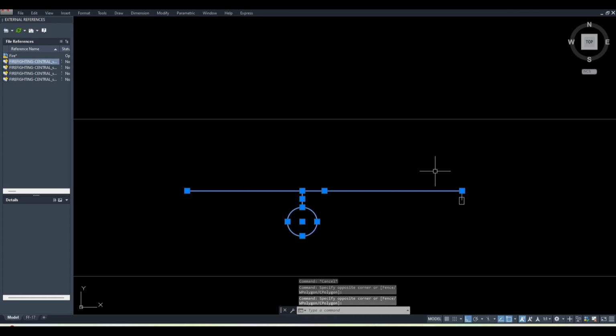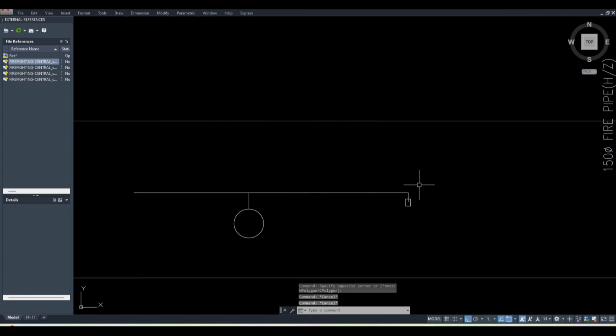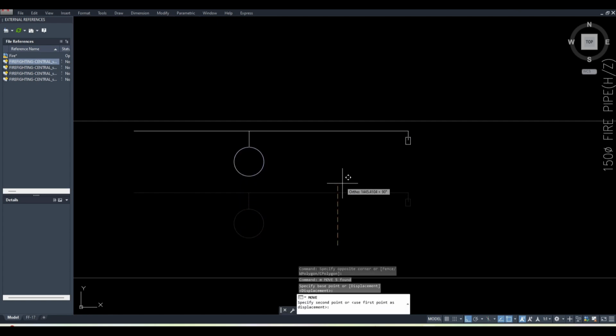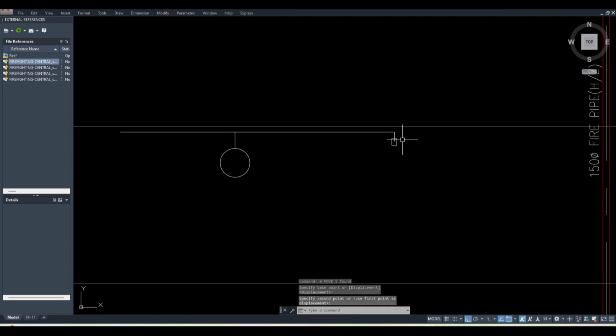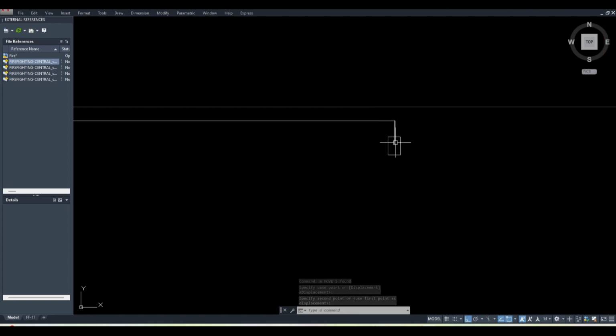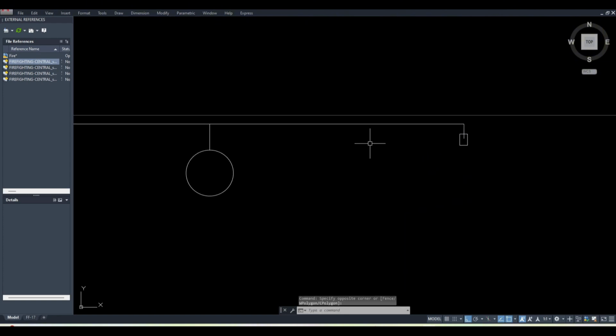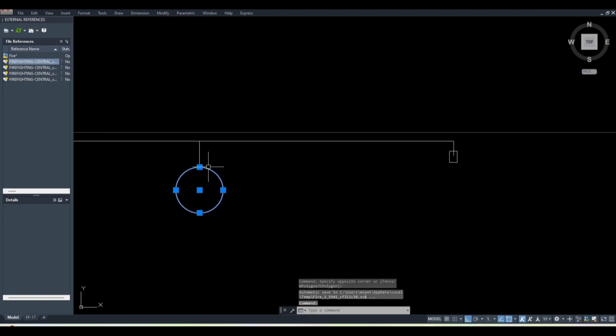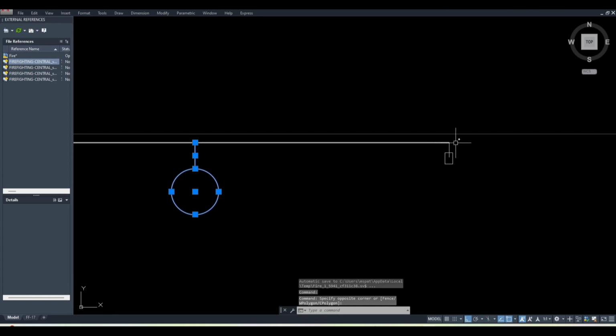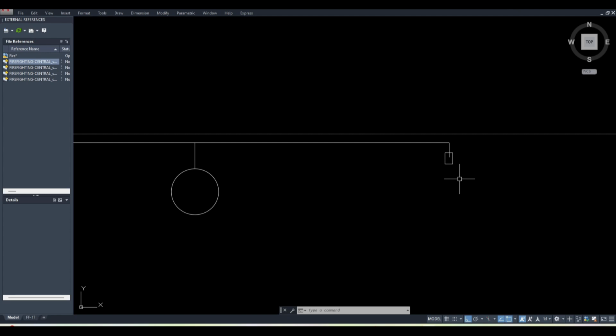And there is a question: can we put the pendant type, not upright type, in the non-ceiling area? Yes, we can do it, as long as you can get it done within the 300 space. But to use a pendant within the 300 space and then connect with the header pipe, it is too difficult to install. That's why we keep it upright, so you can keep it at whatever level you want, and then you can install it upright. So it is easy to install. That's why in the non-ceiling area we use the upright sprinkler, and in the ceiling area we use the pendant sprinklers. Clear?